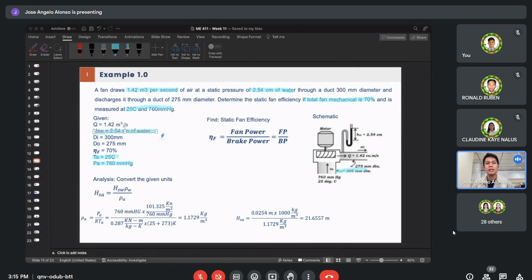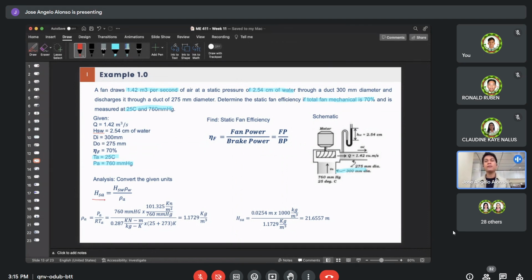So convert muna natin class yung ating static head of water into static head of air using this equation. Static head of air is equivalent to static head of water multiplied by the density ng water divided by the density ng air.